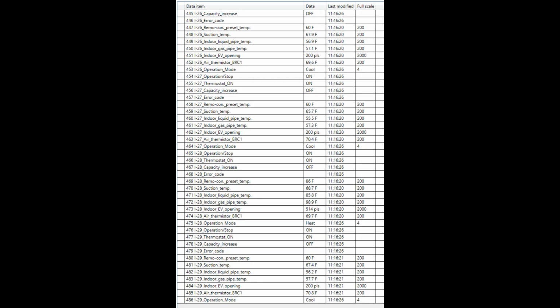So let's look at one of the indoor units in heat mode. How about we take a look at I28? It's all the way near the bottom of our list. You can see that this unit was switched to the heat mode based on the set point and the mode that it's displaying, heat. You can also see that it's receiving the proper hot gas here as well by looking at the indoor unit gas pipe thermistor.